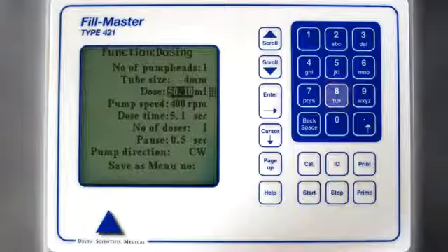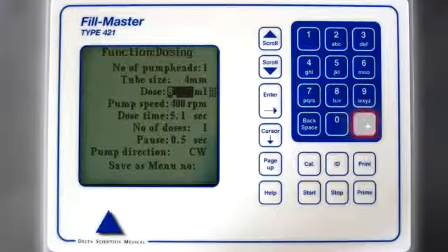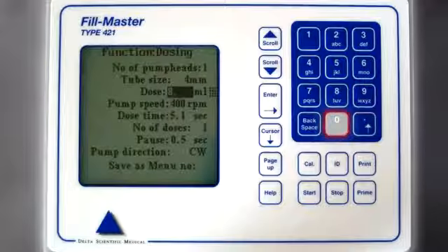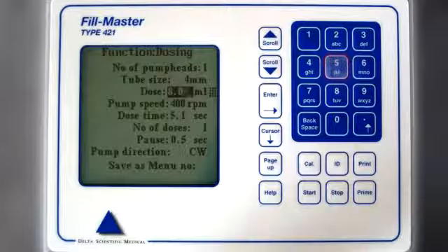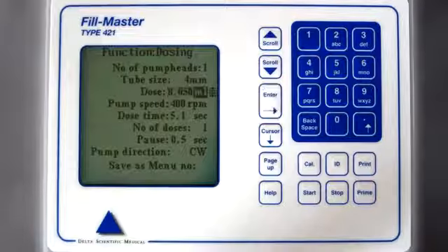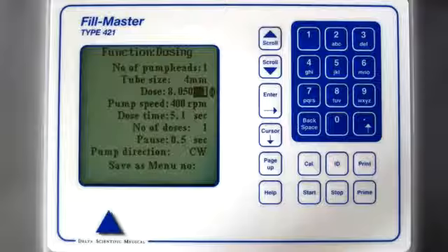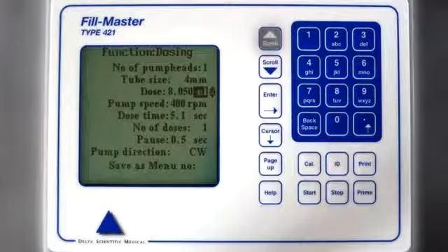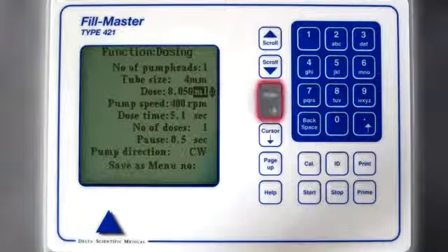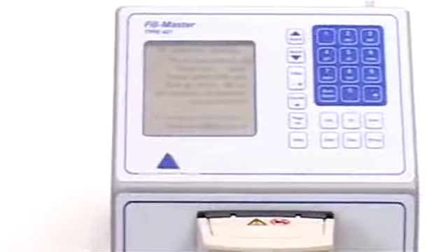With the cursor now in dose, use the keyboard to key in the volume you want and press Enter. Then use the scroll buttons to choose milliliters or microliters or even liters. Confirm with Enter. If you have requested a volume which is either too small or too large to be delivered by the tube size you have chosen, the Fill-Master will give a beep and change the volume setting to show you the smallest or largest volume that can be pumped with your choice of tubing.